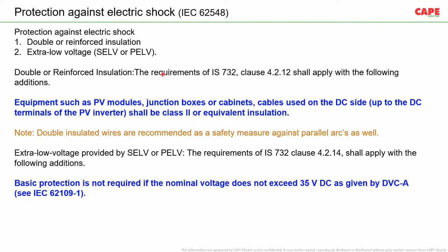So the recommendation in the standard is equipment such as PV module, junction boxes, cabinets, cables used in the DC side up to DC terminal of the PV side shall be class 2 or equivalent insulation. Now, please note that this class 2 means double insulation. Double insulated wires are recommended as a safety measure against parallel arcing as well. So this double insulation also gives safety against parallel arcing.